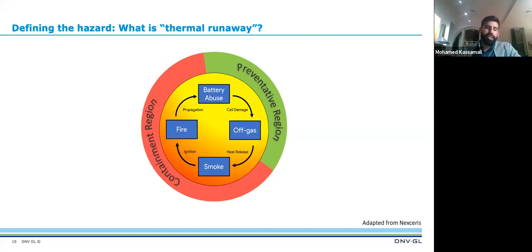Thermal runaway is a phenomenon within battery energy storage systems, specifically lithium-ion batteries, which is an uncontrolled heating within the cell. This may be caused by an overcharge of current or voltage, or even external initiators of temperature—if something next to it is hot, or if there's a fire adjacent to it. This thermal runaway leads to a series of potential hazards we have to keep in mind when considering our design.